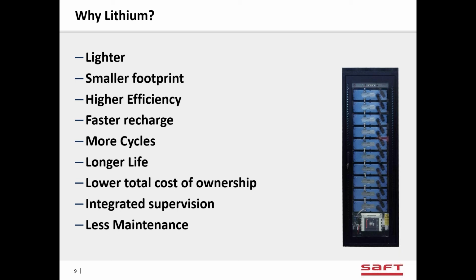Lithium-ion batteries come with an integrated supervision. So all the cells are monitored, the temperatures are monitored. You don't have to add on a battery monitor system because it's already included in the electronics. And there's less maintenance. There's no fluids to top off, there's no vents to check, there's no chemistry to check. The batteries are completely sealed, so your maintenance is really maybe visual inspection and possibly a load test if you want to do it. So we can talk some more about those things.